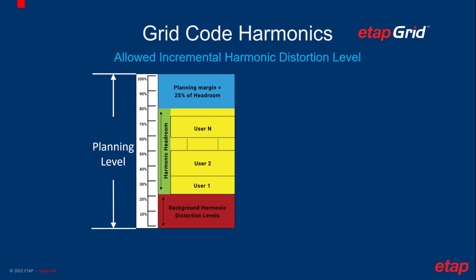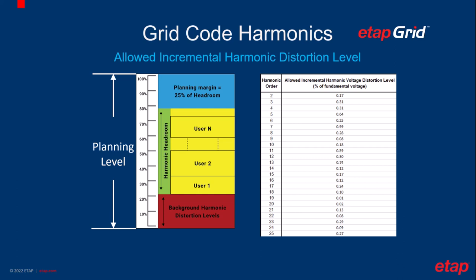When you initiate the application for an interconnection study, the TSO needs to perform a measurement of the existing background harmonic distortion at the point of common coupling for each harmonic order. There is a predefined headroom the TSO needs to maintain for future expansions. Then an evaluation will be done by the TSO by considering the total short circuit capacity of the power grid and the connecting capacity of the new installation. The outcome of this evaluation is an allocated incremental harmonic voltage distortion level for each new installation applicant. The TSO will provide the background harmonic distortion level to the applicant as well.